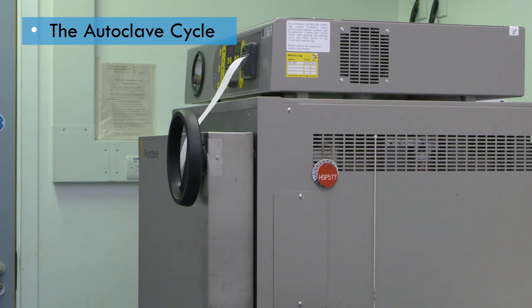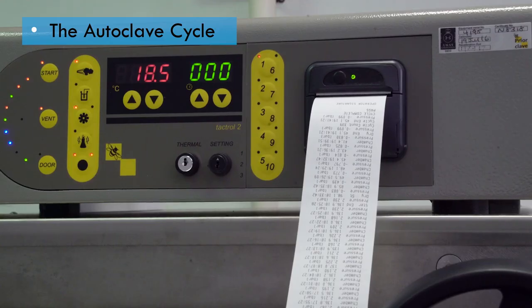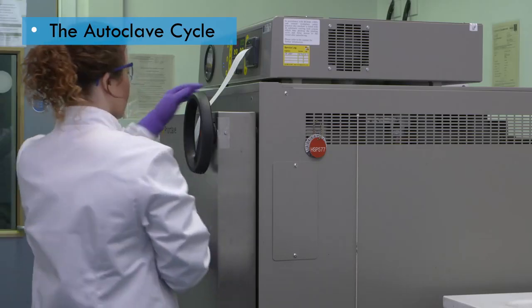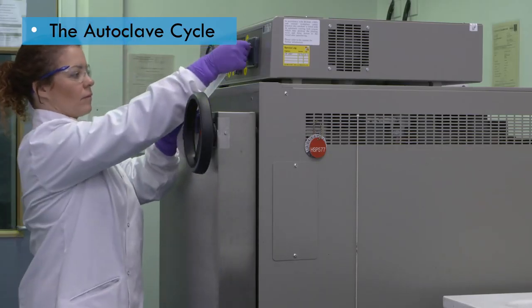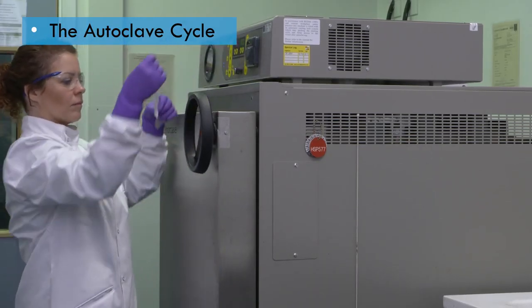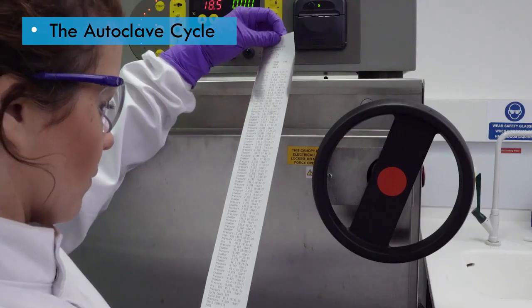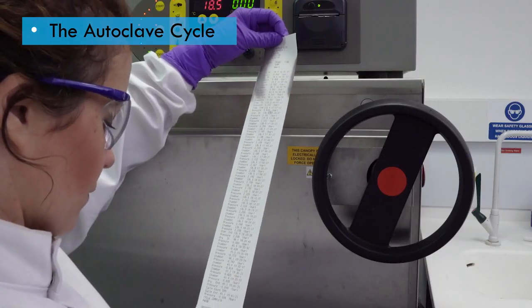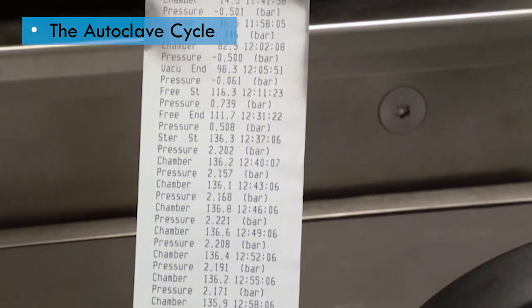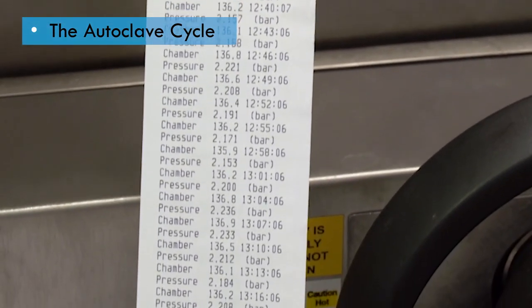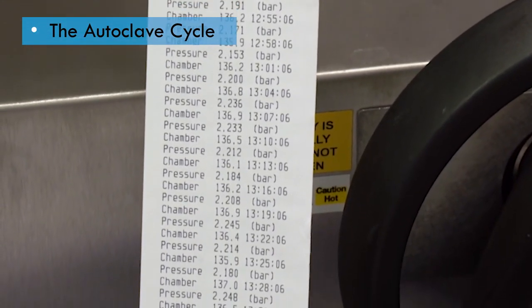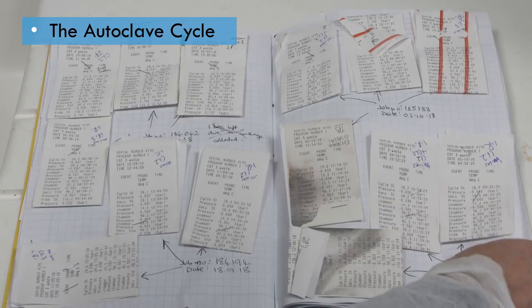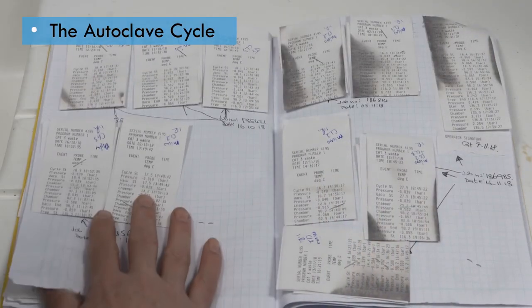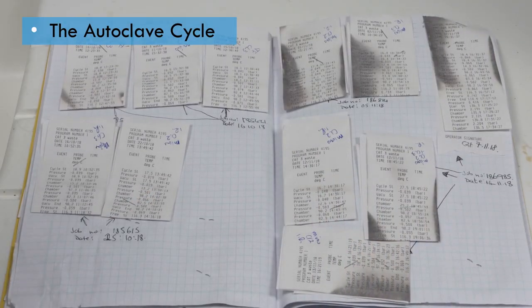If the autoclave has a printout that displays the temperature, it may display the sterilization cycle as a graph or as the temperatures actually achieved. These may fluctuate slightly above and below the set temperature, but this is normal as the heater pulses, so long as it achieves the average over the time period. When the autoclave is serviced, this will be checked and validated.